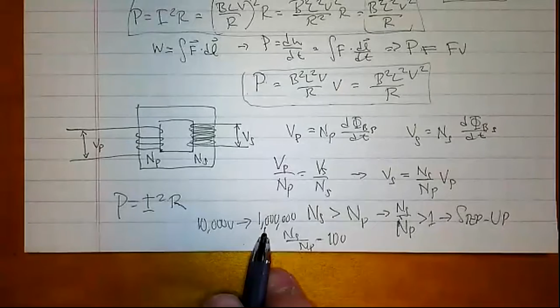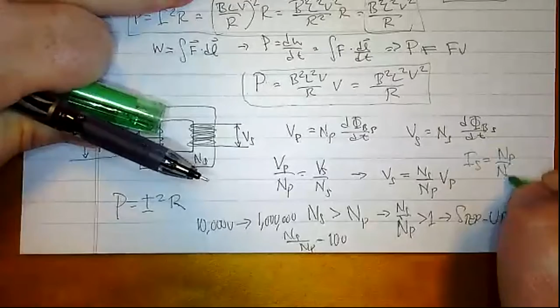But there's a similar equation with these two reversed, I secondary and I primary. So we have another equation: I secondary is equal to N primary over N secondary times I primary. So by cranking the voltage up by a factor of 100, you've cranked the current down by a factor of 100. So instead of 400 times 200, which would be 80,000 amps, you now have 800 amps. So you went by a factor of 100, and 100 squared is 10,000.